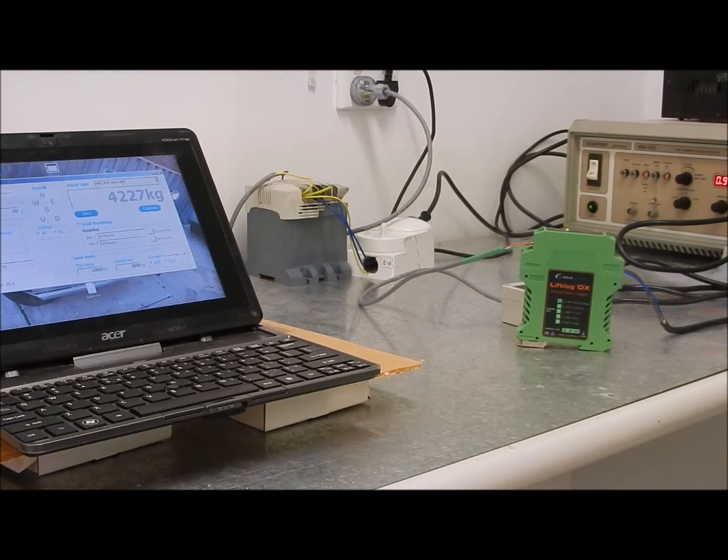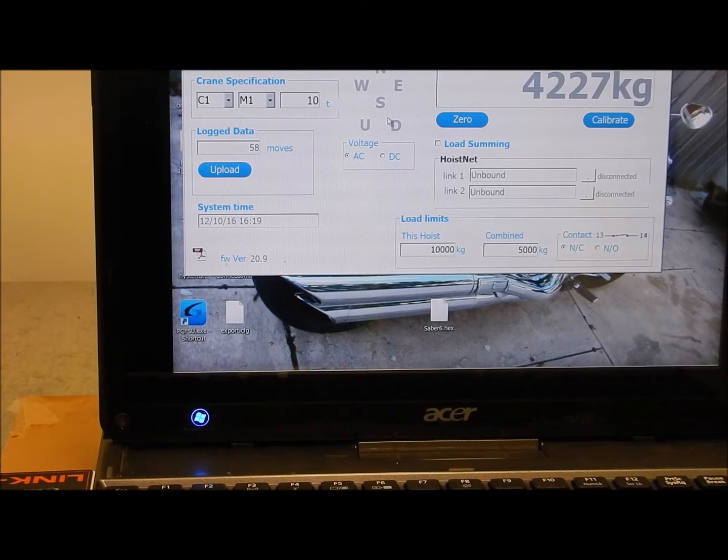Now let's have a look at a lift log. Lift logs are a bit easier to troubleshoot because we can see more. Here we're generating 1 kilovolt spikes and feeding them into the system, and we'll turn that on in a second. You'll be able to see on the laptop, which is connected to the lift log, exactly what that looks like. Okay, so here you can see the inputs north, south, east, west are glitching on and off as these spikes come in. We're generating bursts of spikes here.